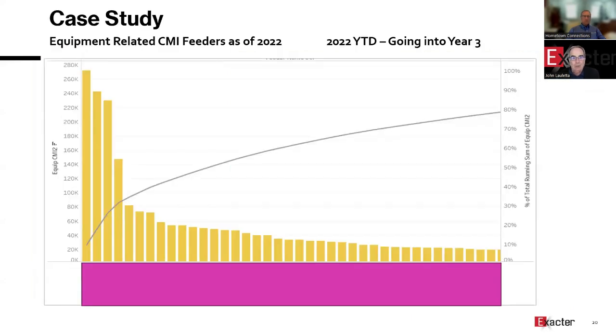When we do our work, we'll sit down with you and gather your reliability information, not SAIDI and SAIFI for all outages like vegetation and animals and other, but just that data that would indicate a failure of equipment. And we'll look at it in a Pareto chart type of analysis. So if you look at this, the yellow bars are different circuits. And as you can see, the first 4 yellow bars represent something like 40% of the customer minutes of interruption for this utility.